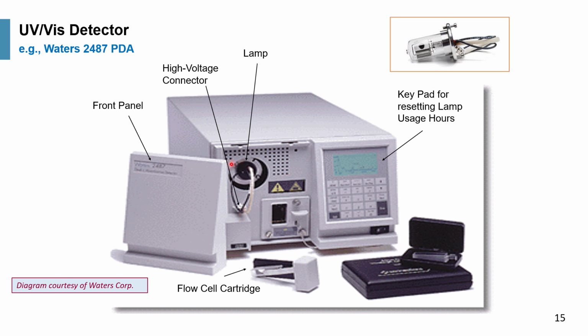And then you would unscrew the two thumb screws using a special tool or your screwdriver, and you pull them out flush, meaning vertically without leaning towards one side. Just take it out, and then you replace it with your new source. One should wear a lint-free cotton glove in the operation, and should always try to avoid touching the windows using your bare hands. Here is the flow cell cartridge. You can examine them, but it's very rarely that it would become dirty, right? In general, that is generally not a problem.